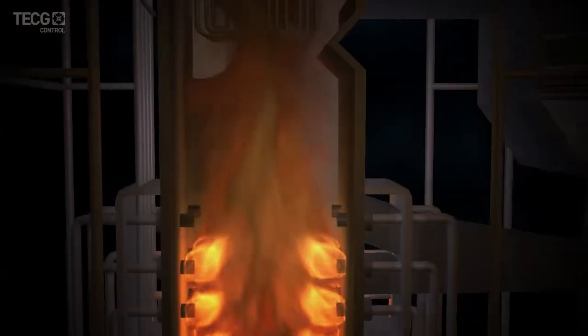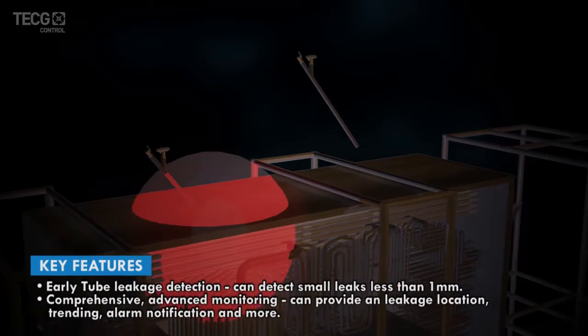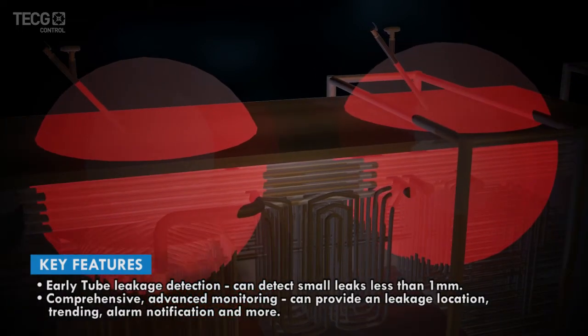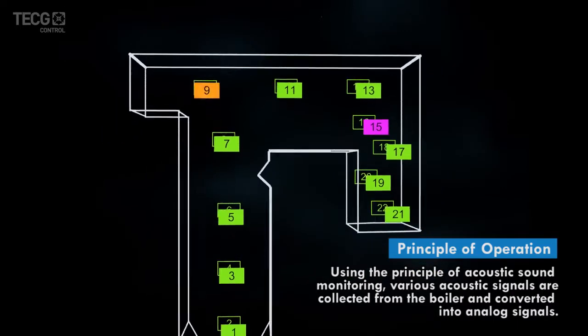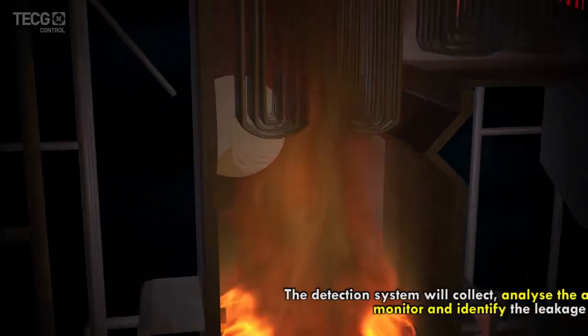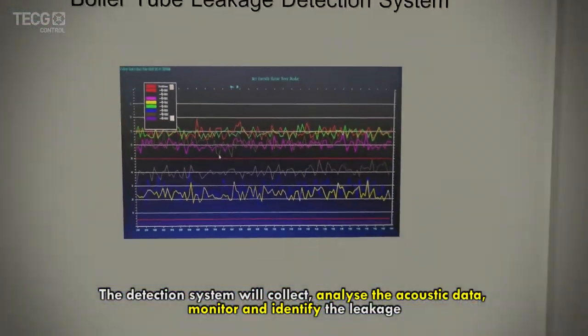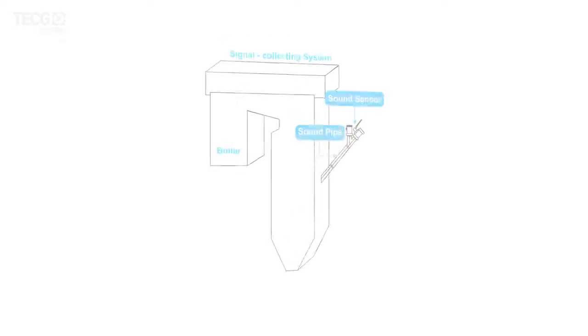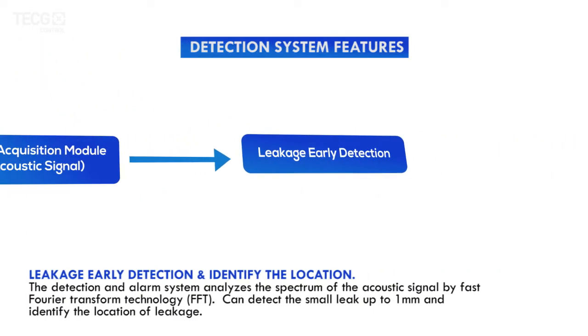Therefore, the early detection and prevention of boiler tube leakage is essential. We offer the advanced BTL detection system that can detect small leaks less than one millimeter and provide comprehensive tube leakage data and alarm notifications. Using acoustic sound monitoring, it covers the water wall, superheater, reheat, and economizer tubes, collecting and analyzing acoustic sound data to identify any leakage across the boiler.